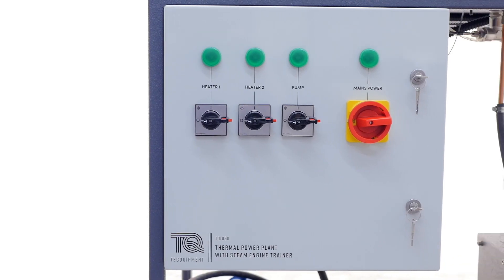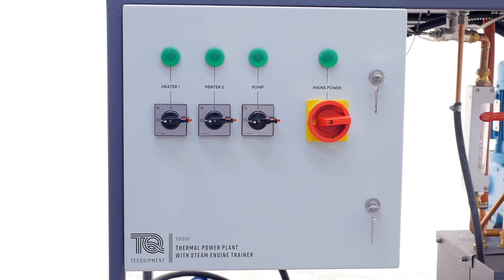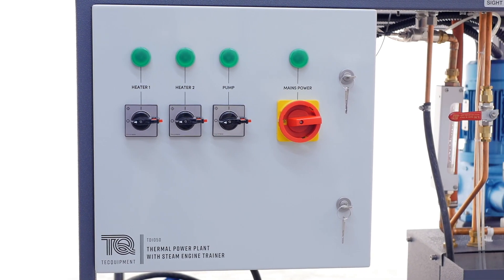To the front there is an electrical control cabinet that contains an isolator and individual control switches with indicator lights for two heater elements and the feed pump. The lights turn off to indicate when the boiler pressure is at peak operating pressure.